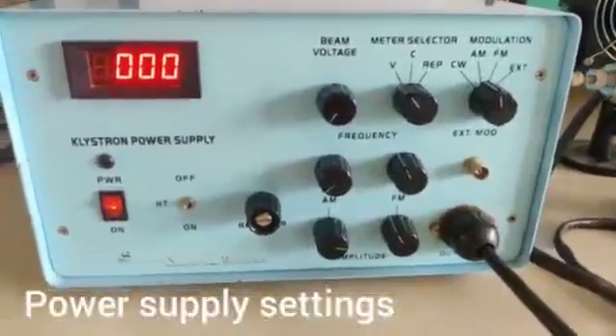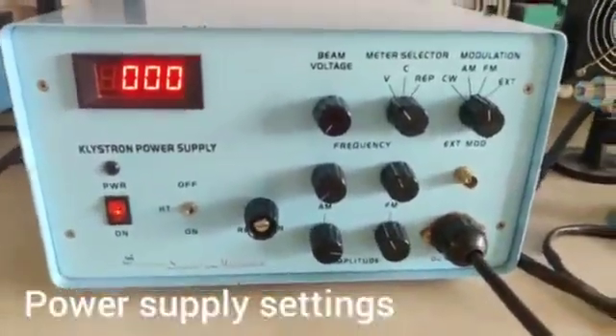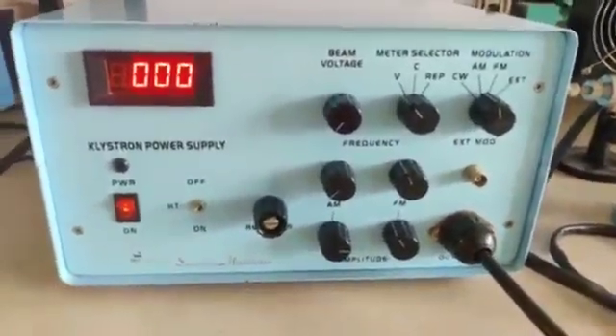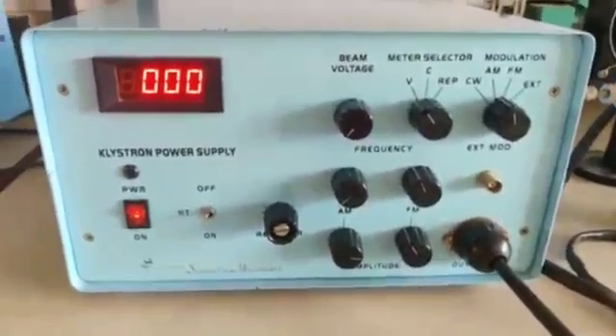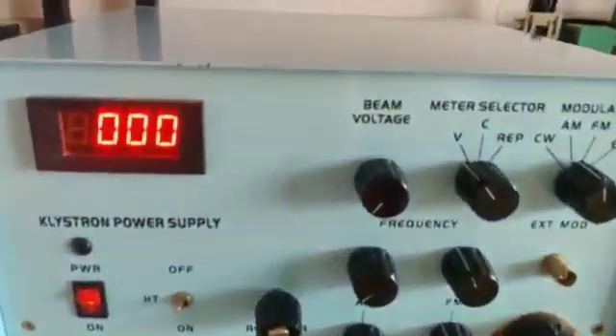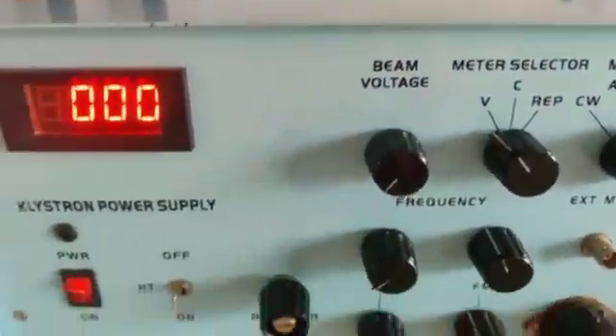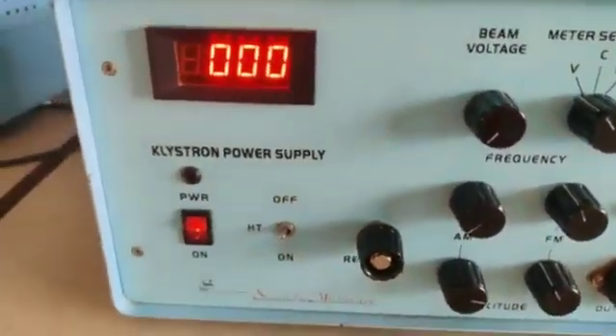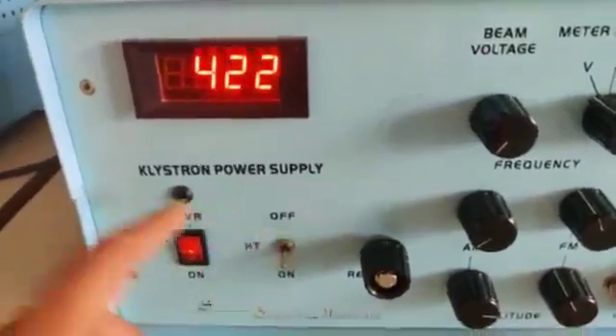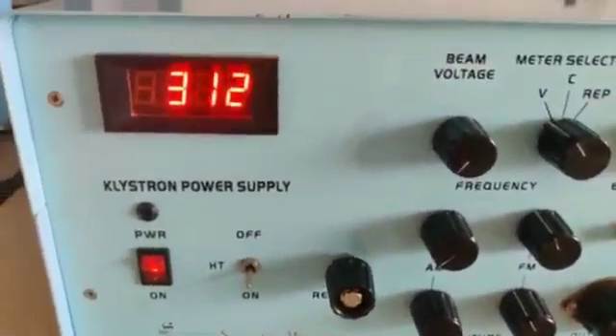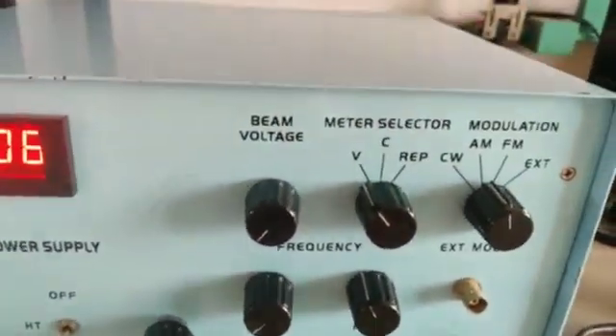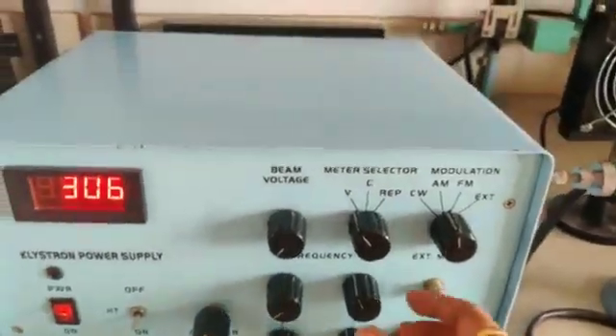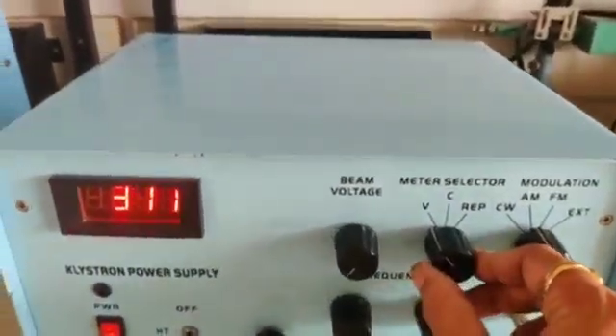Before going to the experiment, we should know the power supply general settings. Here, the beam voltage should always be minimum, and the repeller should always be maximum. This HT should be on. Now here in meter selection, first it should be in voltage.